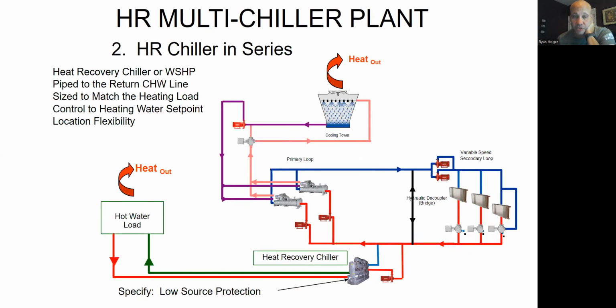The next way I could do this would be putting them in series. What does that mean? This is the same thing, same 3 air handlers over here, same 2 chillers, same cooling tower. Everything's the same right now. And instead of putting a chiller in parallel, I have one in series. What that means is the water coming back from the building gets pulled off that loop. It gets cooled by my heat recovery chiller. Then it gets put back into the same loop and then goes through one of these 2 chillers, right? So it's in series.